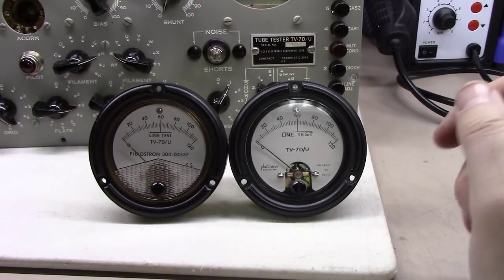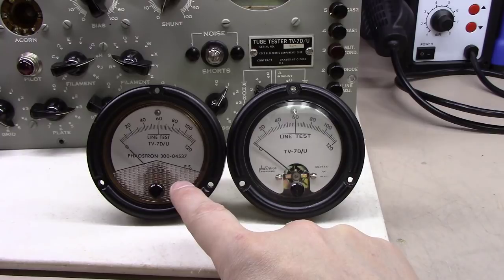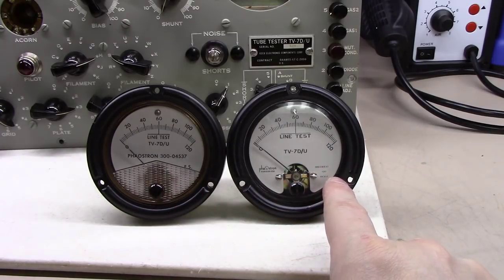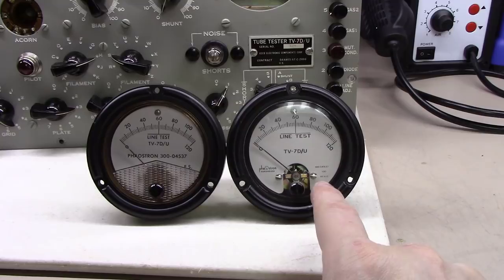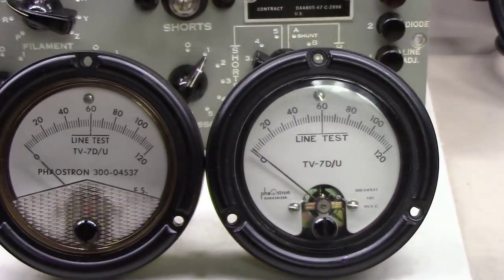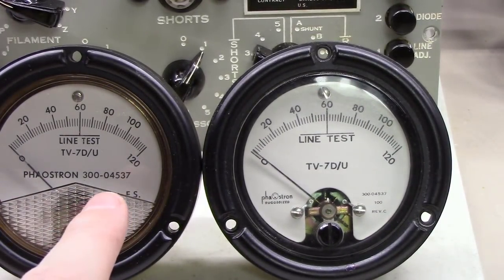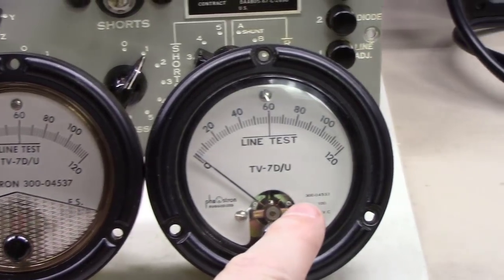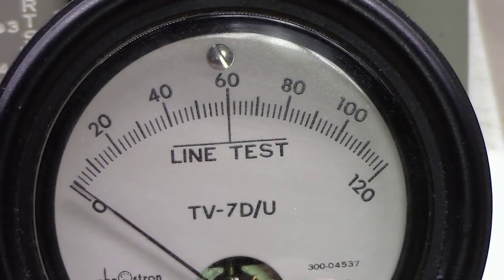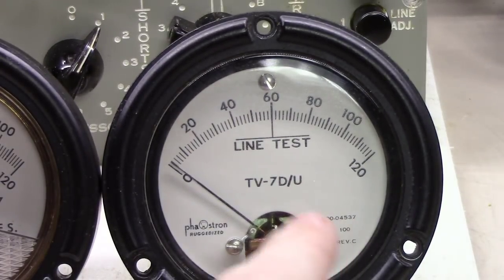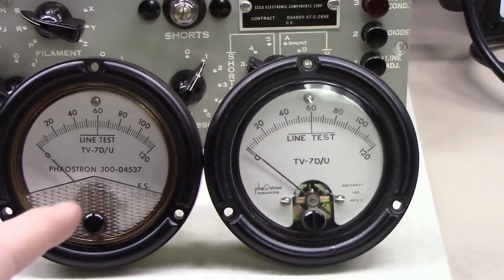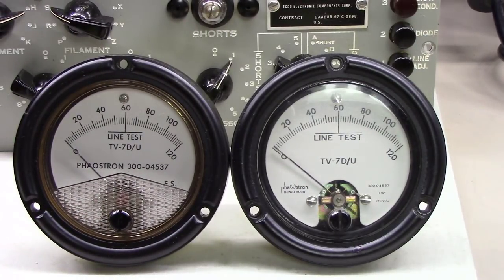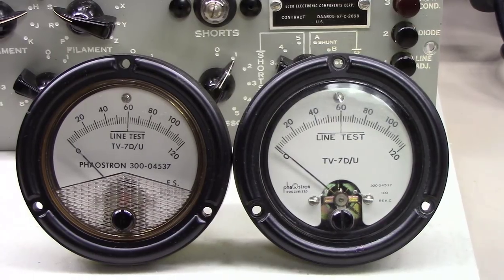Okay, we've got the meter out of this unit at this point in time, which was this one, and this is the replacement meter that we're going to be putting into it. If you'll notice, let me zoom in here, maybe you can see it, but this is part number 300-04537. And if you read the little bitty writing down here, it's 300-04537. This just happens to be a revision C, which is a newer meter than this one was. But internally, electrically, the exact same meter. Both 200 microamps full scale, as well as the same internal resistance.